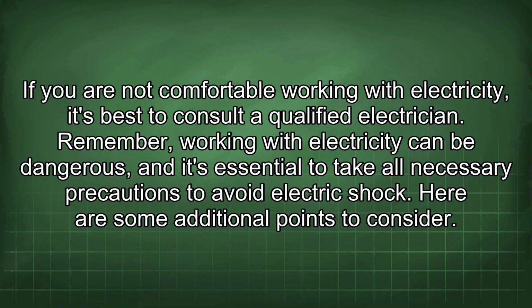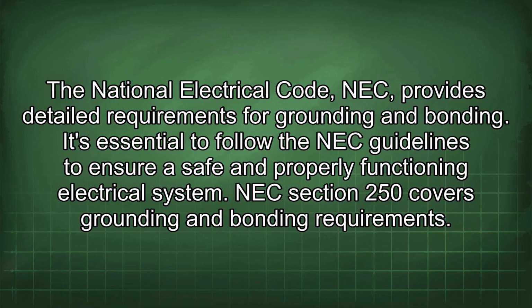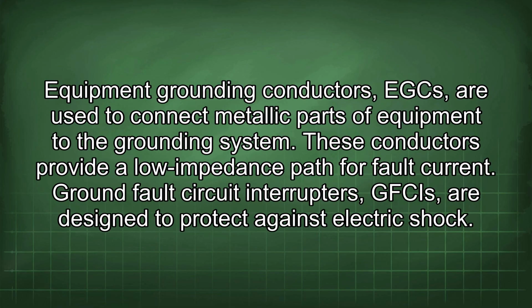Here are some additional points to consider. The National Electrical Code, NEC, provides detailed requirements for grounding and bonding. It's essential to follow the NEC guidelines to ensure a safe and properly functioning electrical system. NEC Section 250 covers grounding and bonding requirements. Equipment grounding conductors are used to connect metallic parts of equipment to the grounding system. These conductors provide a low impedance path for fault current.